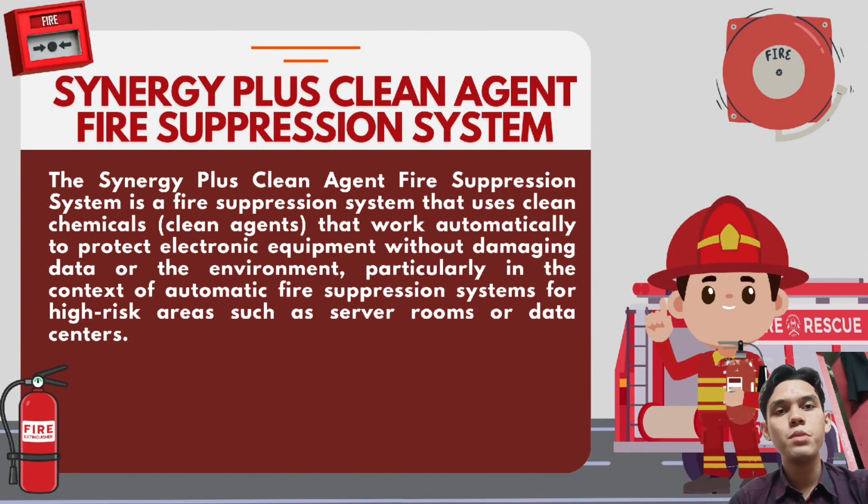Okay, this video demonstrates the Synergy Plus Clean Agent Fire Suppression System, specifically designed for high-risk areas such as server rooms and data centers. Because these rooms operate continuously, they are highly susceptible to electrical short circuits and overheating. The system works by integrating a smoke detector, a control panel, and a canister containing a clean agent, FK5112.